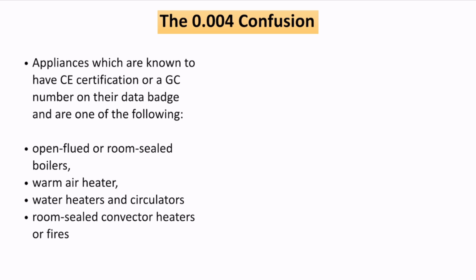Some schools say that any reading of any appliance, as long as it's below 0.004, is fine, and anything above 0.004 fails. It makes it a lot easier for you as students, but in reality there are rules around this. That only applies if the appliance has a CE certification, like we spoke about before, or a GC number on their data badge, and the appliance must be one of the following: an open flued or room sealed boiler, a warm air heater, a water heater or circulator, or a room sealed convector heater or fire. So that applies, but it only applies in those circumstances.